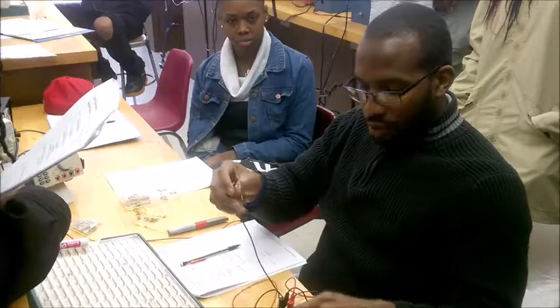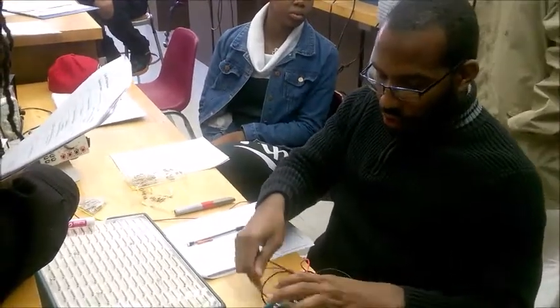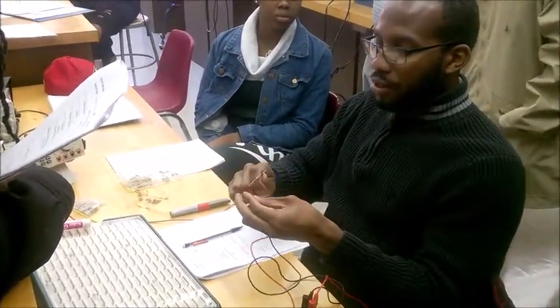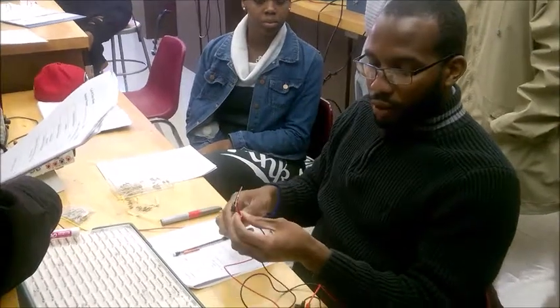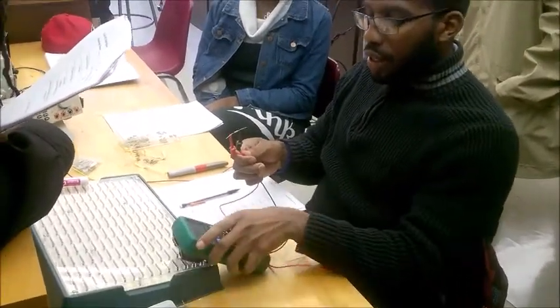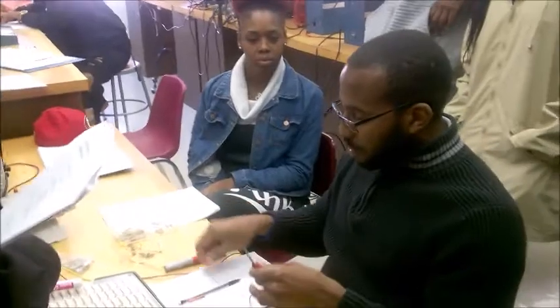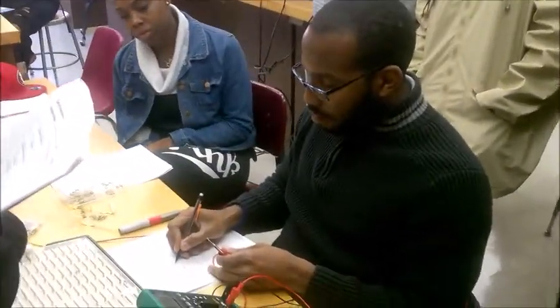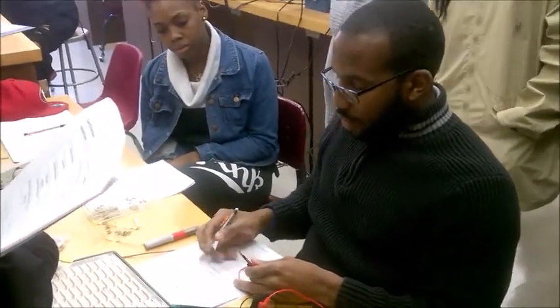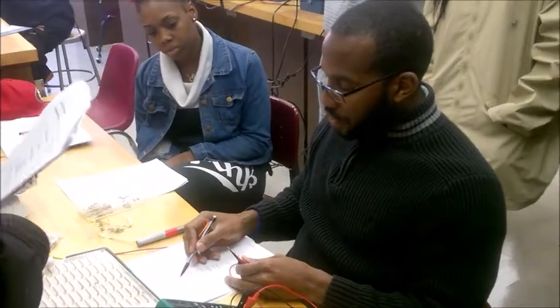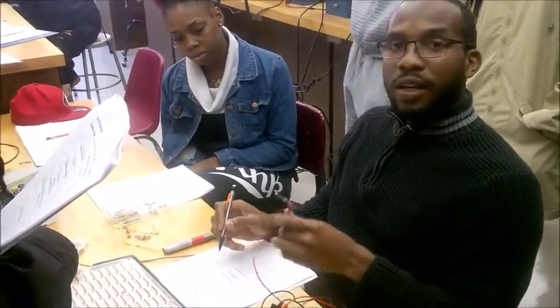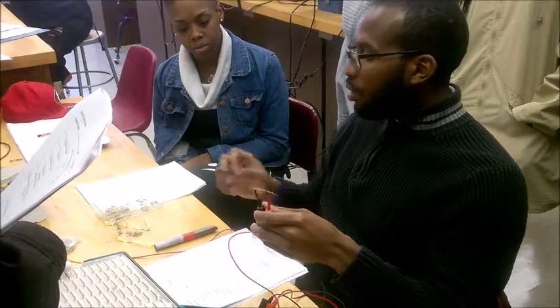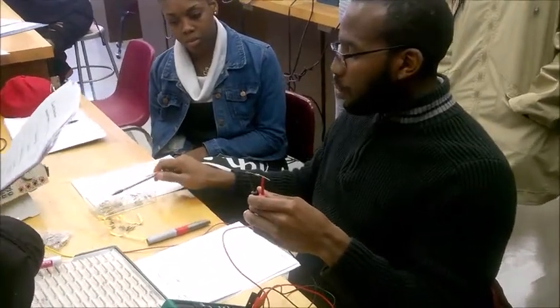Now I can do this just by turning this to resistance and measuring the resistance. Okay, it comes to 99.6 ohms. So I read this here, 99.6 ohms. And it says, is this within the range? Yes, it is within the range. So I just put a check right here. Now you need to do this not only for this one, but you have this one and you have one of these ones as well.